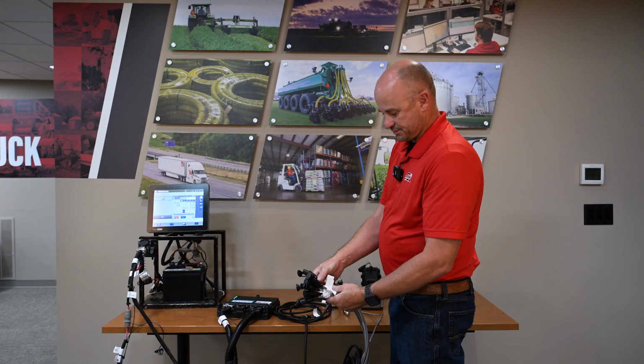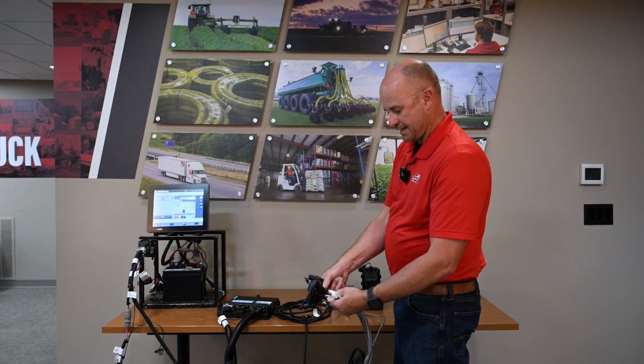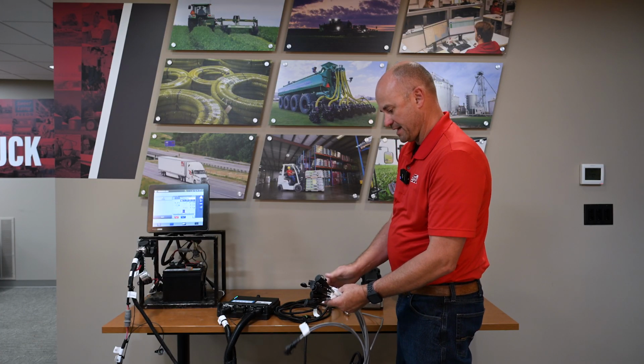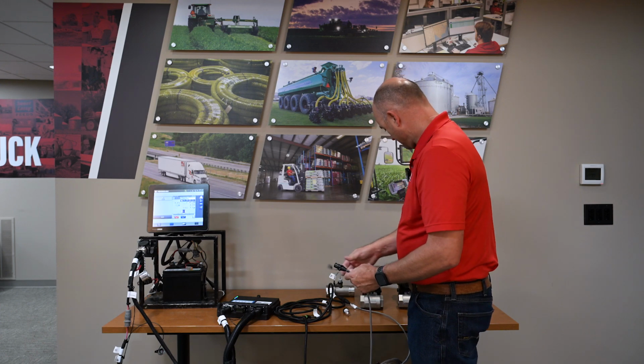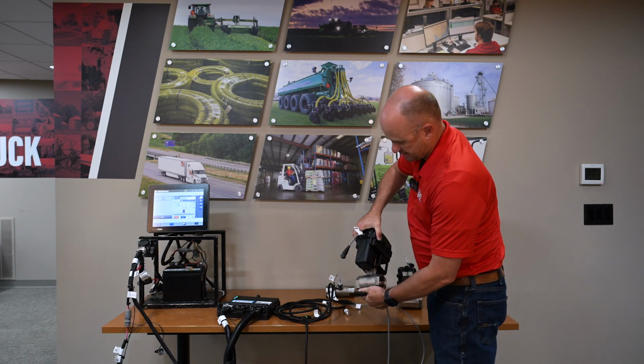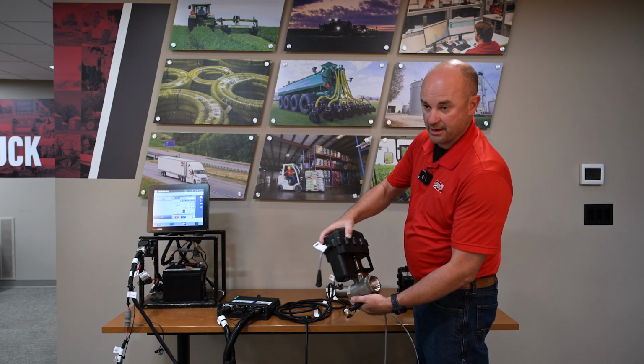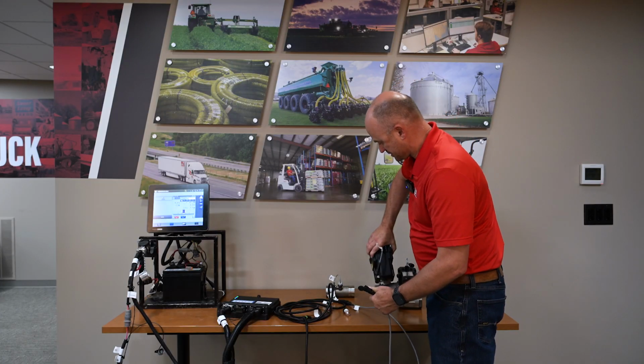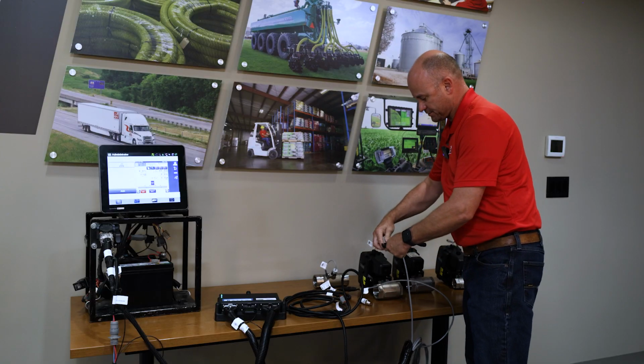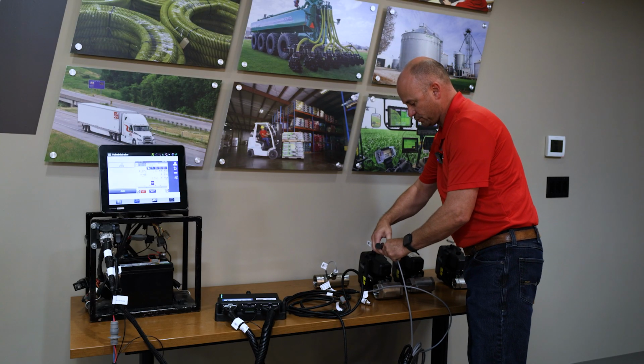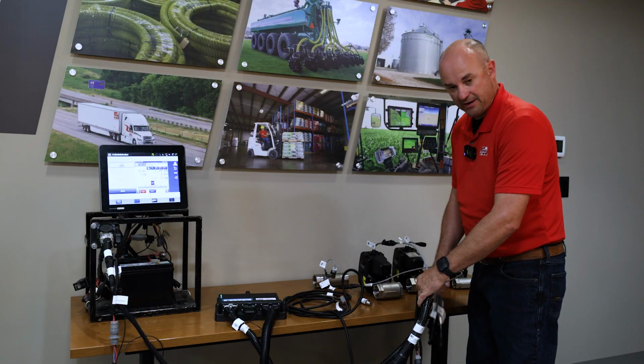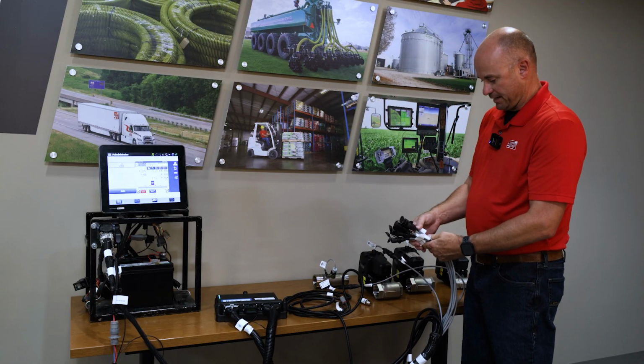On a 2-valve system, we'll go through the tags. Those are all sections. Here's our master on off. Our master on off valve is the valve that does not have the silver sticker on it. Technically, it is just a standard on-off valve whose job is to shut the flow off to the cooler so you don't have vapor coming out of your cooler the entire way around the end.